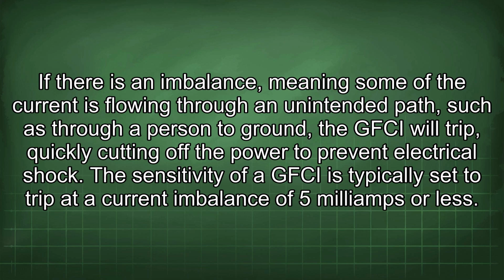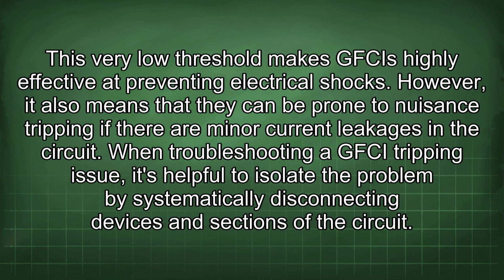The sensitivity of a GFCI is typically set to trip at a current imbalance of 5 mA or less. This very low threshold makes GFCIs highly effective at preventing electrical shocks. However, it also means that they can be prone to nuisance tripping if there are minor current leakages in the circuit.